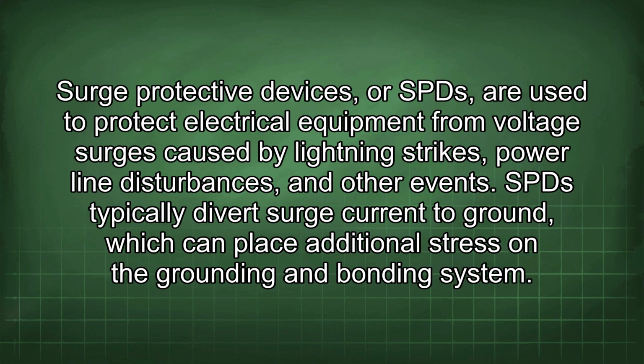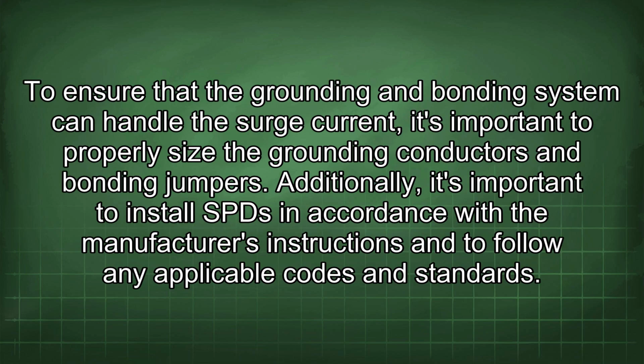Surge protective devices, or SPDs, are used to protect electrical equipment from voltage surges caused by lightning strikes, power line disturbances, and other events. SPDs typically divert surge current to ground, which can place additional stress on the grounding and bonding system. To ensure that the grounding and bonding system can handle the surge current, it's important to properly size the grounding conductors and bonding jumpers. Additionally, it's important to install SPDs in accordance with the manufacturer's instructions and to follow any applicable codes and standards.